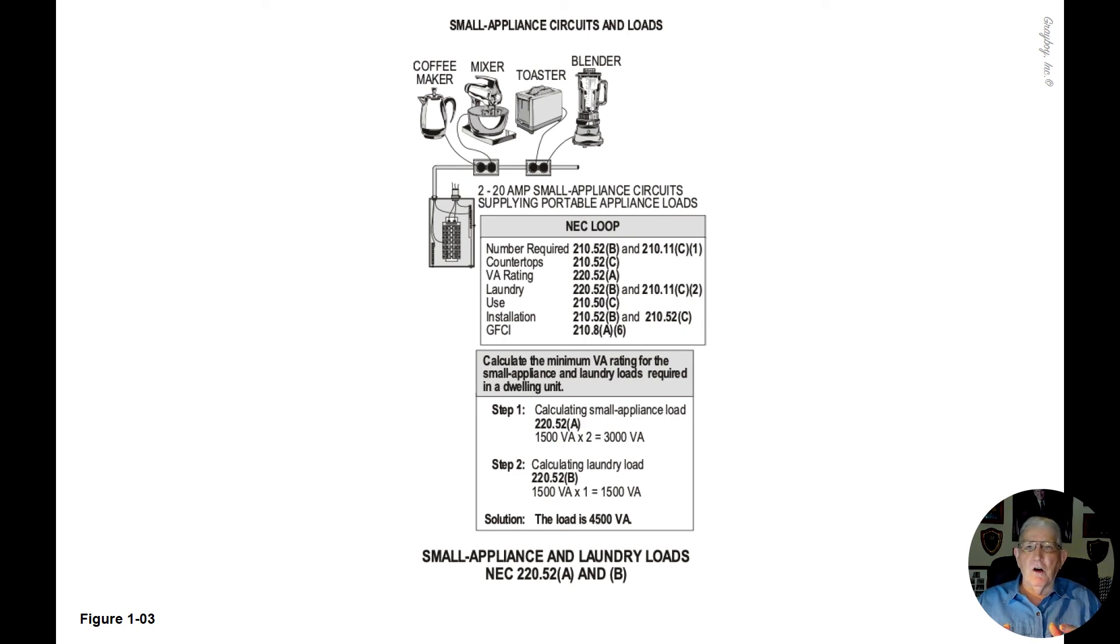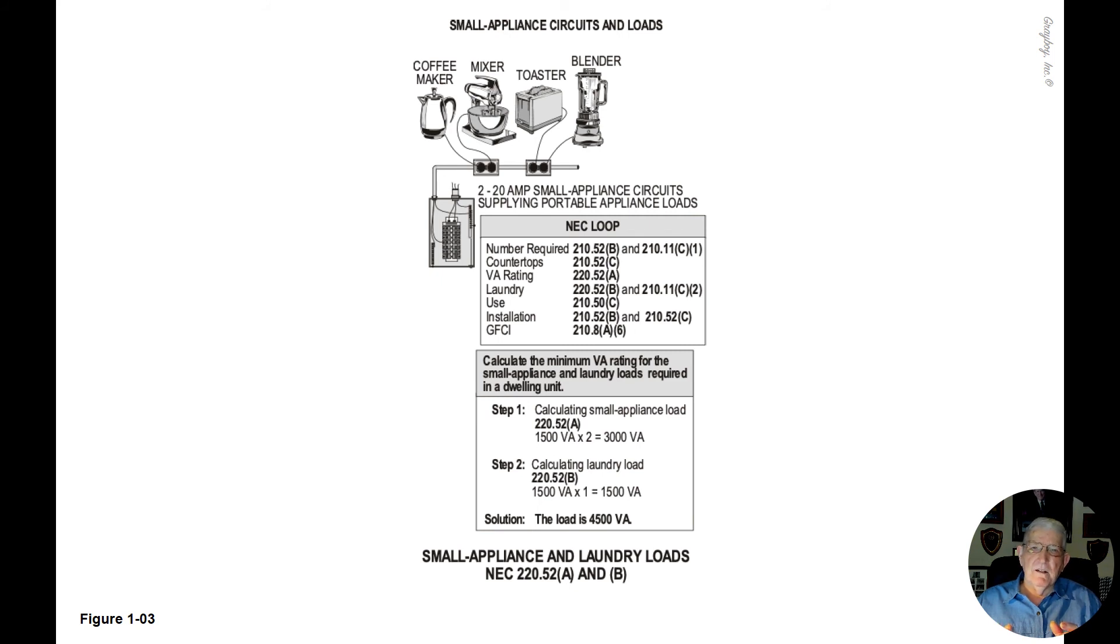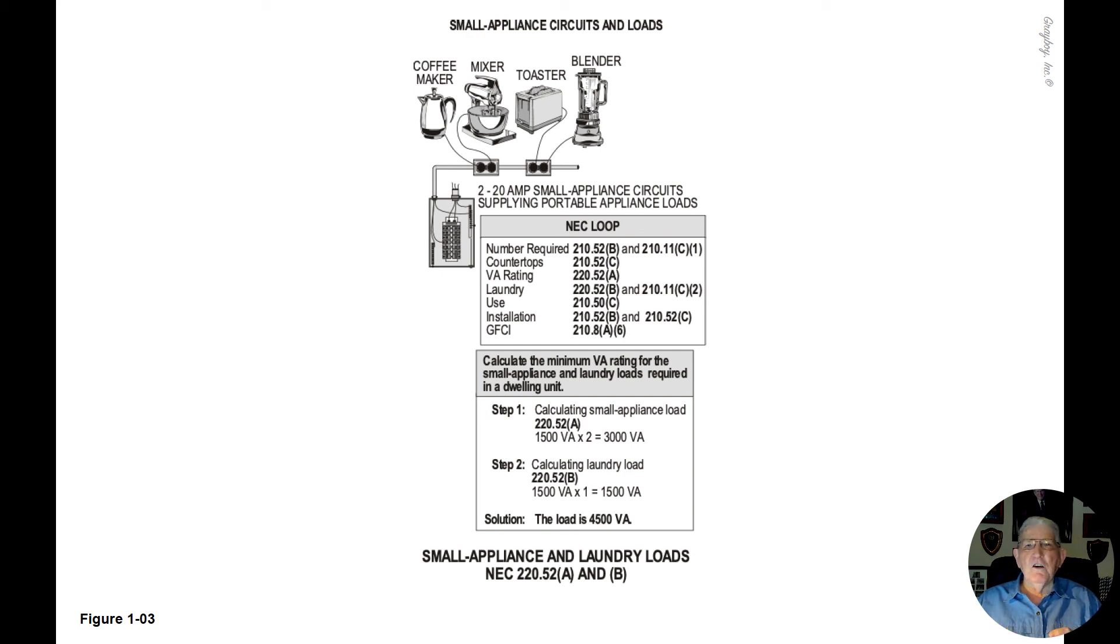Step one, calculate the small appliance circuits for the kitchen, pantry, dining room and breakfast room. 1,500 VA each for these circuits and there's two of them which would be 3,000 VA.